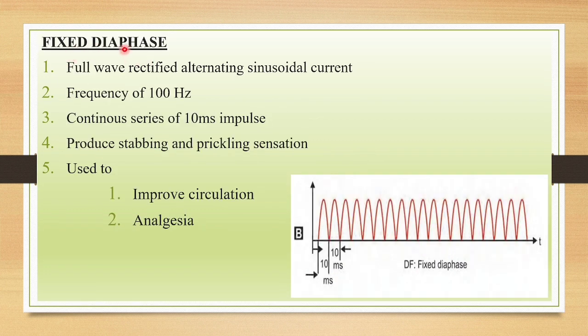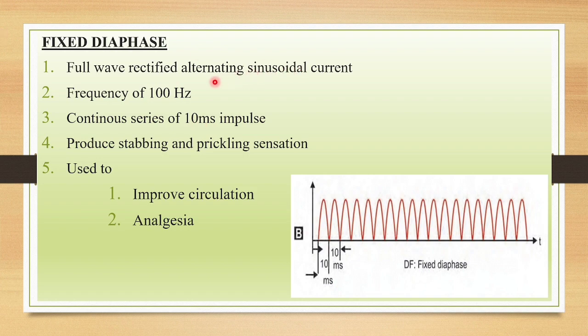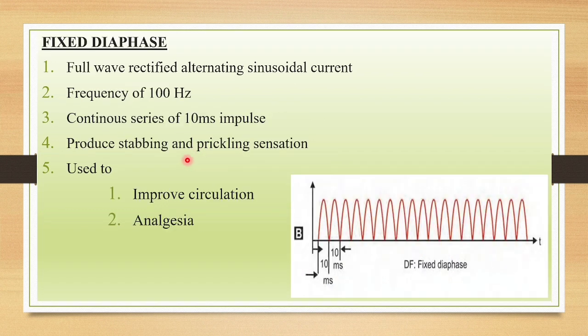The next mode is fixed diaphase, which is full wave rectified — an alternating sinusoidal type of current. The frequency will be 100 Hz and it produces a continuous series of 10 millisecond impulses. This mode may produce stabbing and prickling sensations. Fixed monophase produces vibration sensation for a prolonged period of time, while fixed diaphase produces stabbing and prickling sensations and can be used to improve circulation and reduce pain.